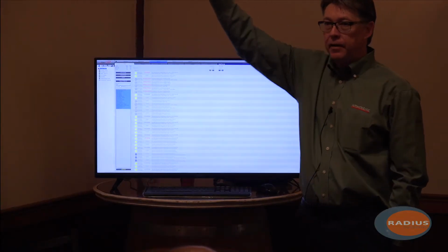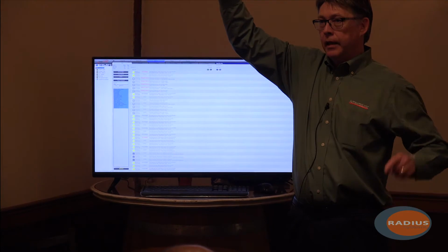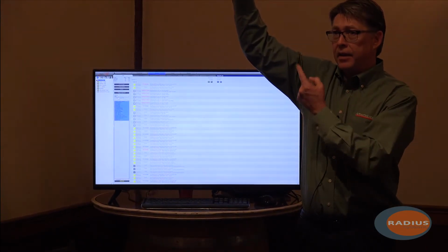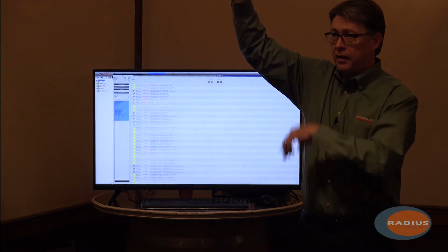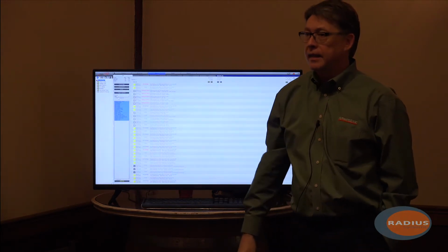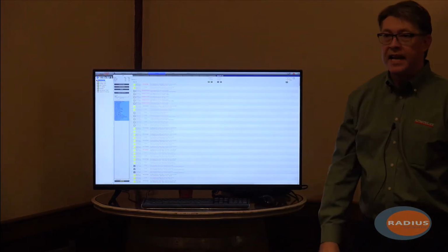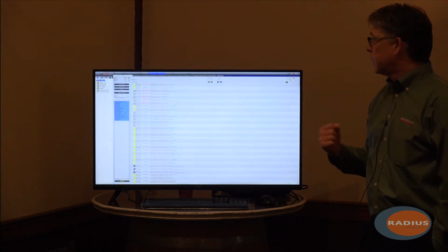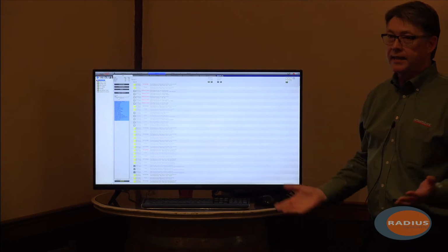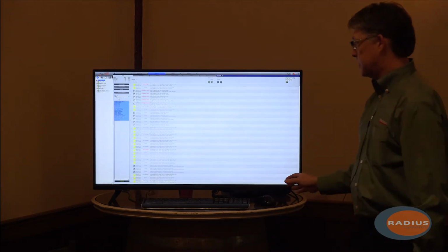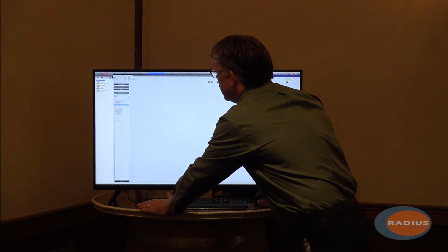Wouldn't it be awesome if, when your air handling unit goes down, your VAVs that are downstream of it, that know they're connected to that air handling unit, don't tell you anything because they're like, we know the air handling unit's down. That's hierarchical alarm suppression. That's one of the standard cascading alarm suppressions, another term they use. That is a standard fault detection and diagnostic algorithm that's built into the Web Control system.